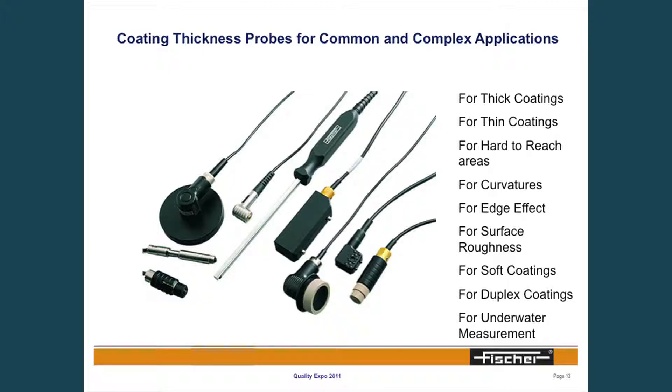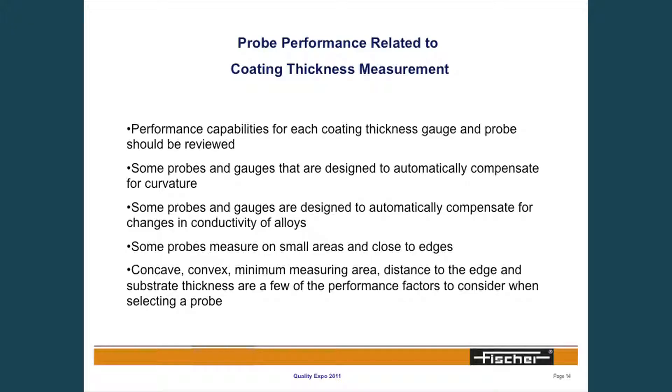There are different probes for different applications. We have probes ideally suited for rough surfaces, probes designed for very soft coatings so I don't indent the probe into the surface, and double-pronged probes for measuring on rough surfaces. Different geometries are available depending on where you need to take the measurement. Probe performance includes the capability of the probe, the trueness and repeatability, and the ability to measure on those different geometrical surfaces.